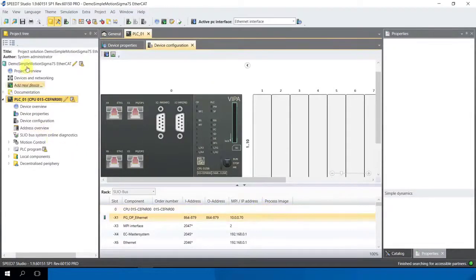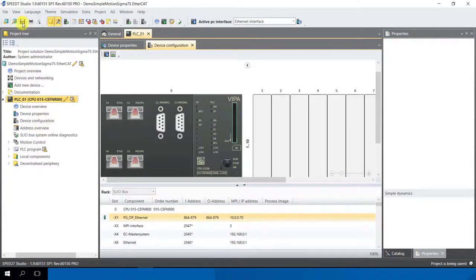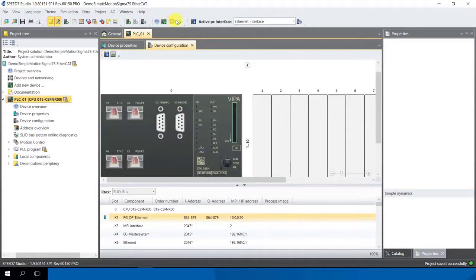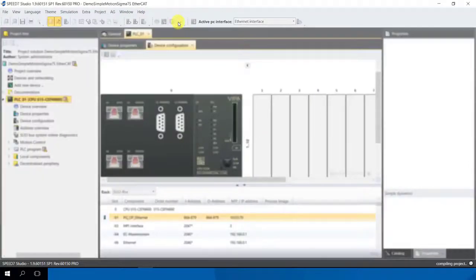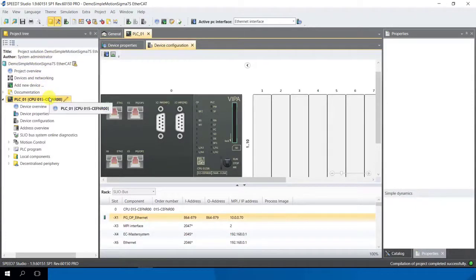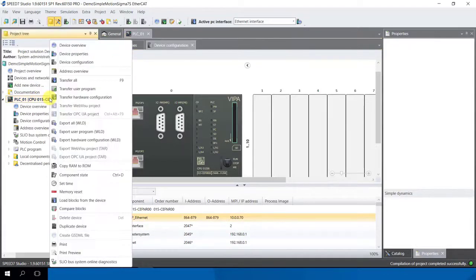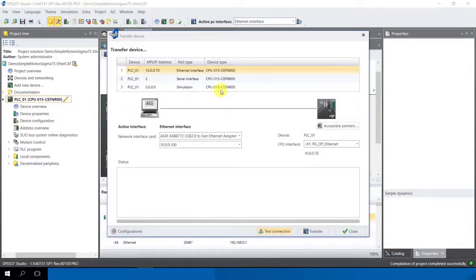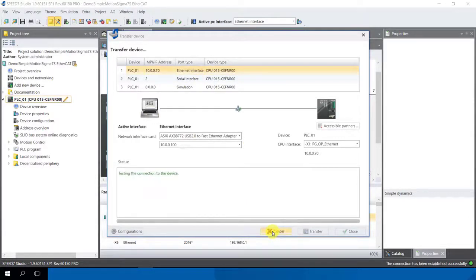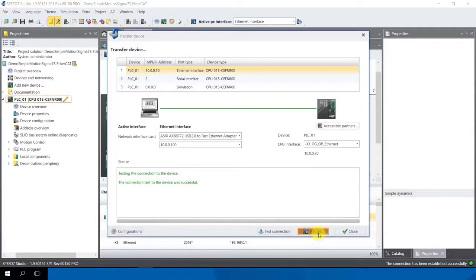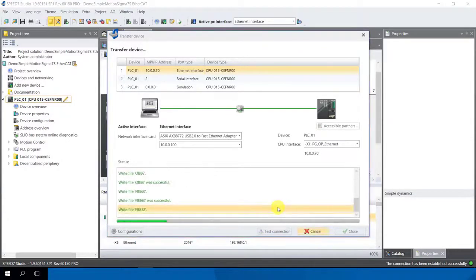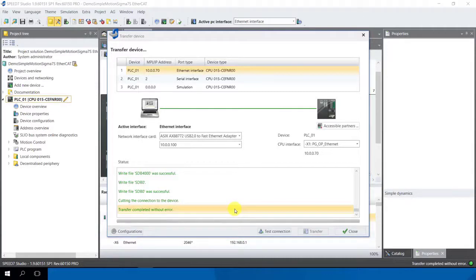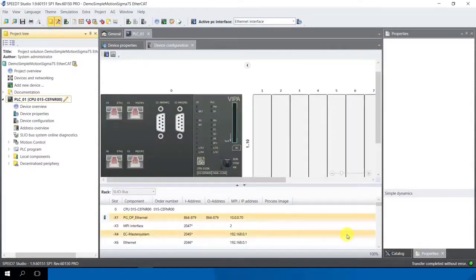After that we can save the project. You'll find on the status bar here an icon to save it and also we compile this project, this demo project with the hardware container. This takes a few seconds and after that I can transfer also the hardware container and the software container in the PLC. I click on my project with the PLC, right mouse click and I say here transfer all. After that appears a window and here we can make a test connection if everything is okay and here we see the connection test to the device was successful. Very nice and we confirm it to transfer all this project in the PLC. Very nice, everything is green and the transfer completed without error. Now we can close this.